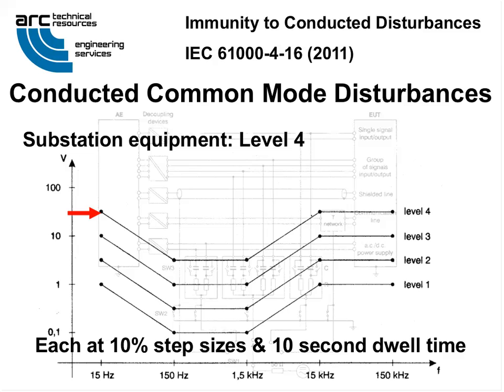We usually see an audio amplifier used for the first 3 segments up to about 15 kilohertz. And then an RF amplifier is brought in for testing from 15 kilohertz to as high as a megahertz, certainly to 150 kilohertz, using 10% step sizes and a 10-second dwell time, while the acceptance of the EUT is assessed to the criteria I will show you.